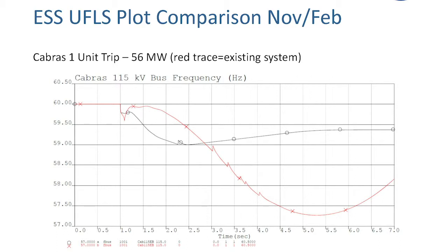This just kind of gives you an idea of what we've been talking about. What you're looking at here is a simulation. If you look up on the left-hand side of the plot, where they both start out as a straight line, that's 60 hertz. So that's what you want your power system to look like. The black line is what happens if you trip a generator with energy storage. And you can see you go down to 59 hertz, and you come back up, and you will eventually recover to 60 hertz. The red line is what happens if you don't have energy storage.